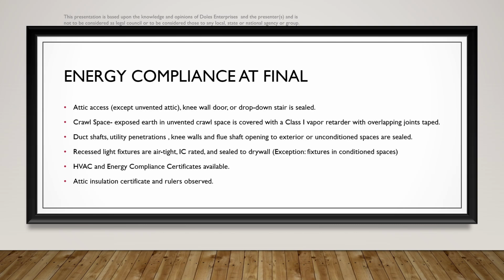Attic access, except unvented attics, knee wall doors, or drop-down stairs, must be sealed. Concerning crawl spaces, exposed earth in unvented crawl spaces shall be covered with a Class 1 vapor retarder with overlapping joints taped. Duct shafts, utility penetrations, knee walls, and flue shaft openings to the exterior or unconditioned spaces shall be sealed. Recessed light fixtures shall be airtight, IC rated, and sealed to the drywall. The exception is fixtures in conditioned spaces.